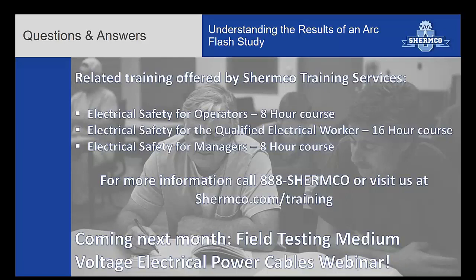Yeah, so with molded case circuit breakers, there can be a big difference in the time it takes them to open on a dead short. You probably want the faster acting ones to reduce arc flash values, but once again, you have to be in that fast acting zone with this arcing current to even get there.